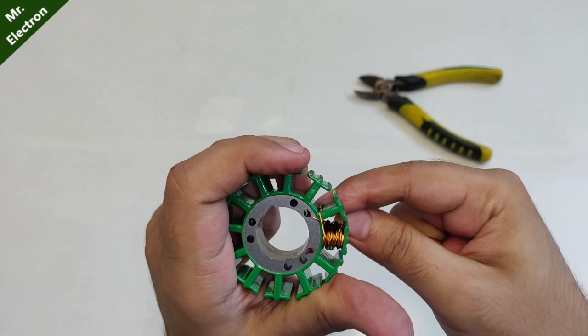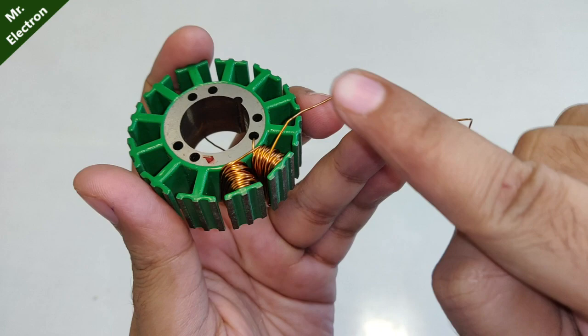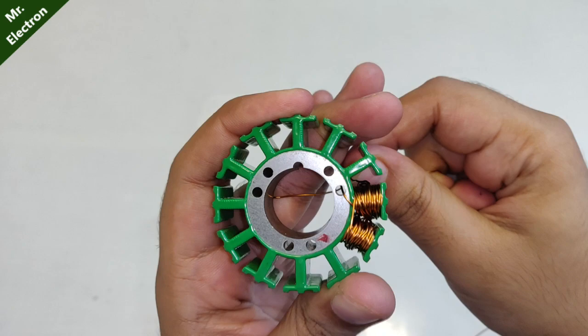Now guys, initially we were going in the clockwise direction, but after completing two poles you have to go counterclockwise for the next two poles. One turn, two turns, three turns, and same 25 number of turns per pole.